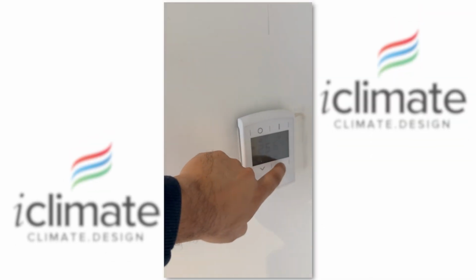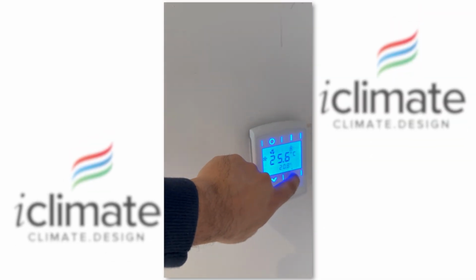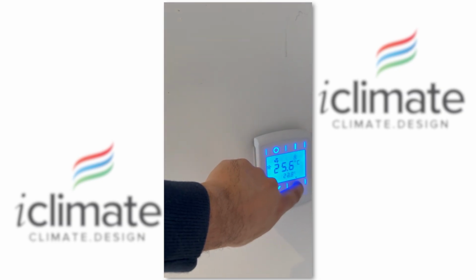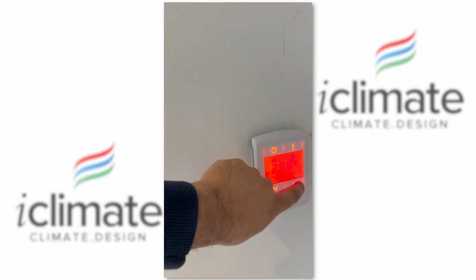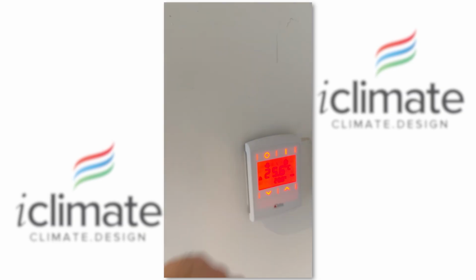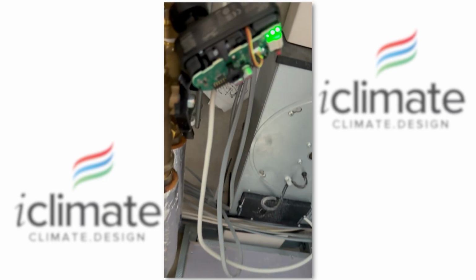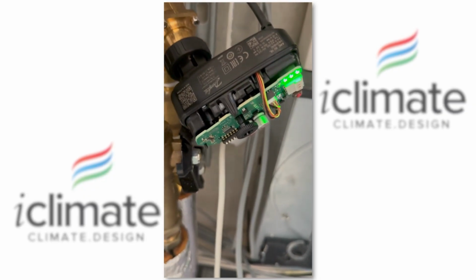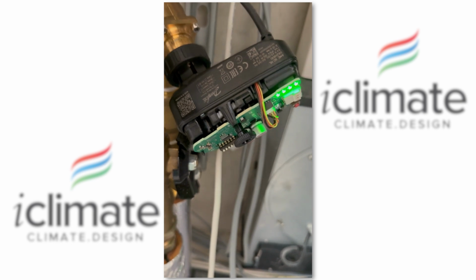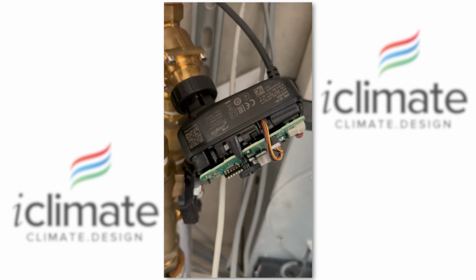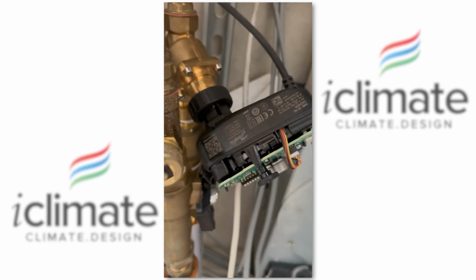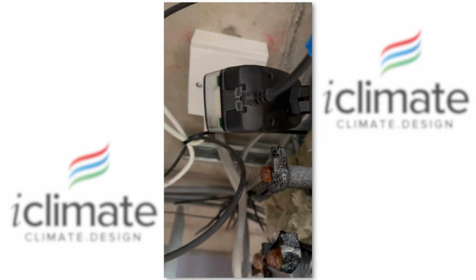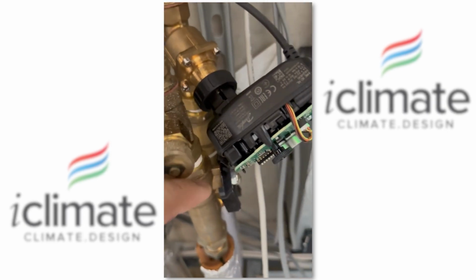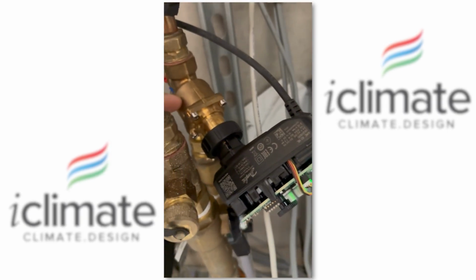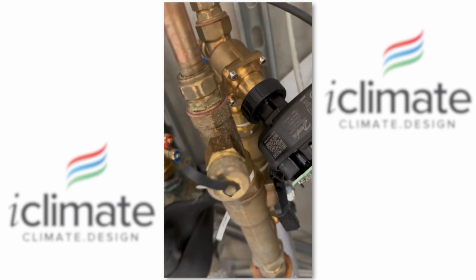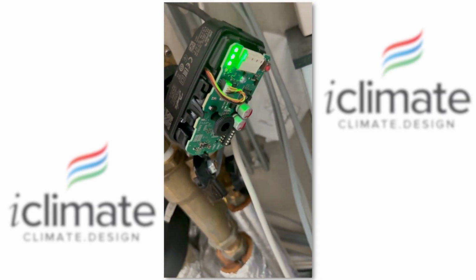Let's test heating. We have 25 in the room currently. Turn the set point up to 28. We now look at our heating valve actuator there. You can see that it is driving the valve with the flow through the PICV. And then we're going to verify that we have flow through here. This PICV has been balanced according to the flow rate of our fan coil unit.